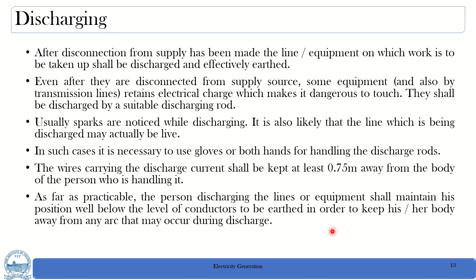The discharging rod should be brought near to the circuit slowly, and if any arcing or flashover is noticed, then it shall be withdrawn immediately. A report on such arcing or flashover shall be made to the person who issued the LCP, that is the line clear permit. Normally, the assistant engineer will be the person who issues these instructions for the operators or the lineman. Each and every conductor, including the neutral, shall be discharged as shown above, and all the conductors after discharging shall be short circuited together and earthed effectively as per the prescribed procedure.